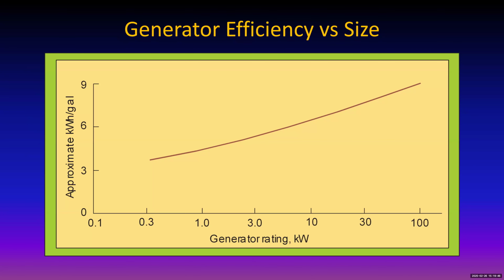The bigger the generator, generally the more efficient. And what we're looking at here is how many kilowatt hours you can get out of a gallon of fuel if we're using a gasoline generator, for generators from between, say, 300 watts up to 100 kilowatts. Notice the log scale on the horizontal axis and the linear scale on the vertical axis. So in general, larger generators are more efficient. There's less heat loss, and more of the energy is converted into rotating mechanical energy.